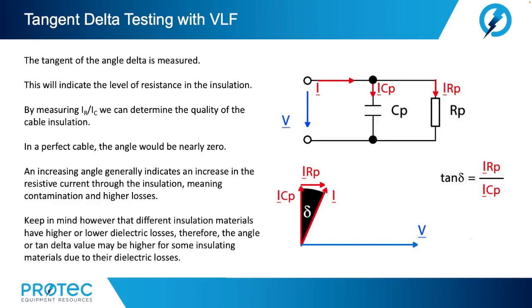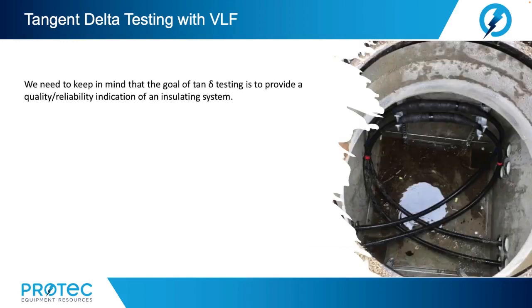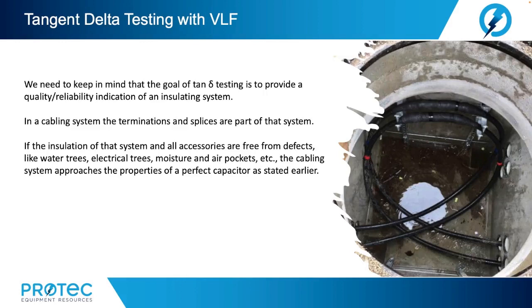Keep in mind, however, that different insulating materials have higher or lower dielectric losses. Therefore, the angle or tan delta value may be higher for some insulating materials due to their dielectric losses. We need to keep in mind that the goal of tan delta testing is to provide a quality reliability indication of an insulating system. In a cabling system, the terminations and splices are part of that system. If the insulation of the system and all accessories are free from defects like water trees, electrical trees, moisture, air pockets, etc., the cabling system approaches the properties of a perfect capacitor as we had stated earlier.